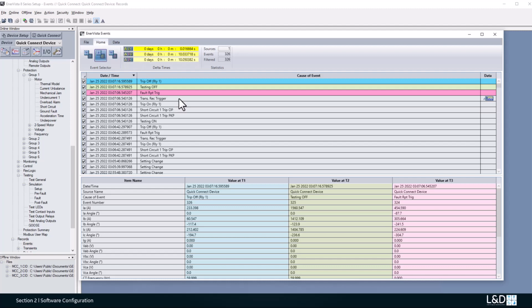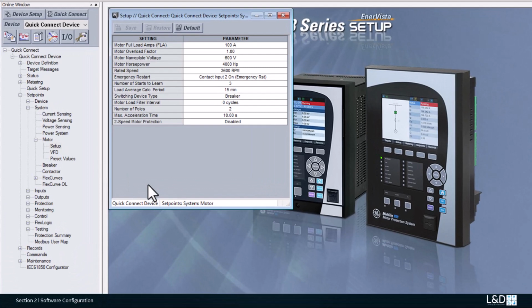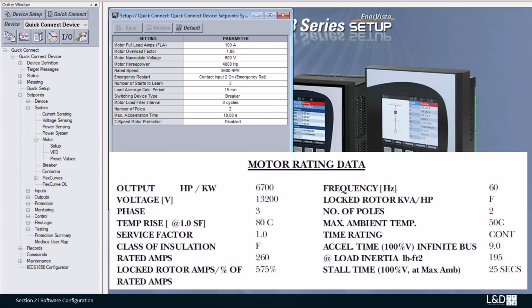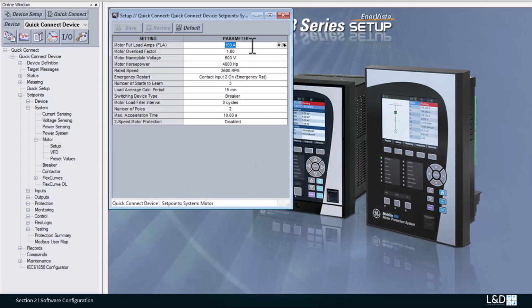And the 859 can record a maximum of 2048 events, which is more than the 512 events in the 369 and 1024 events in a regular 8 series relay. Under the motor setup, the nameplate parameters can be entered here, like the FLA, service factor, rated voltage, etc. In this example, we're going to set the FLA from the default 100 to 260 amps.